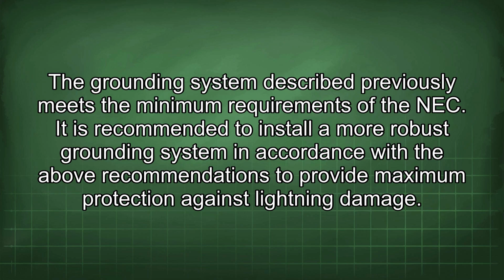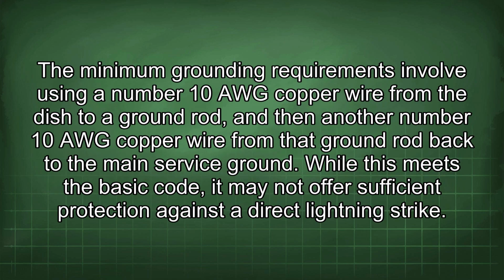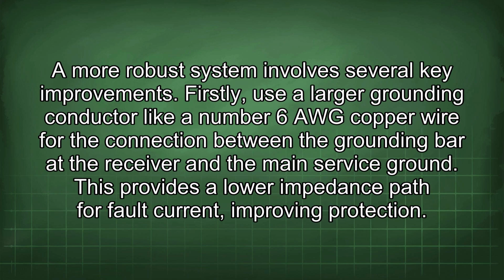It is recommended to install a more robust grounding system in accordance with the above recommendations to provide maximum protection against lightning damage. The minimum grounding requirements involve using a number 10 AWG copper wire from the dish to ground rod, and then another number 10 AWG copper wire from the ground rod back to the main service ground. While this meets the basic code, it may not offer sufficient protection against a direct lightning strike. A more robust system involves several key improvements.